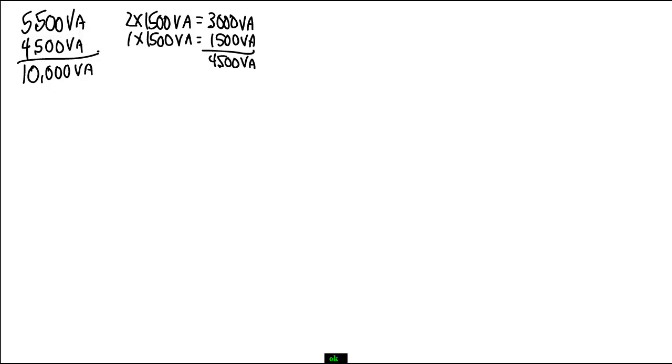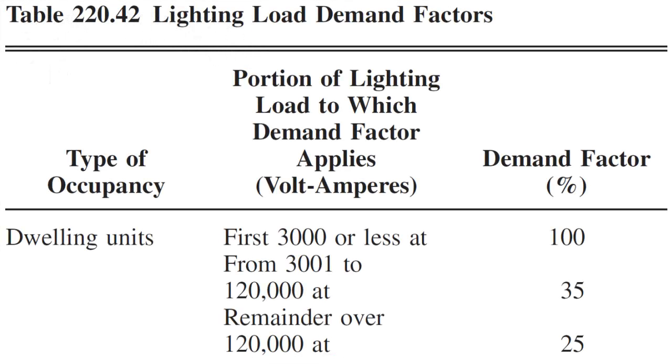So the question in the last class was, what do you do next? Well, here's the answer since nobody looked it up or tried to give it to me. The answer is found in table 220.42, our lighting load demand factors.